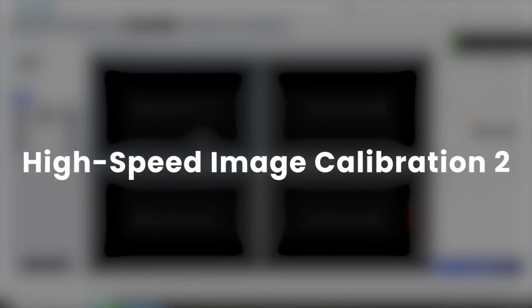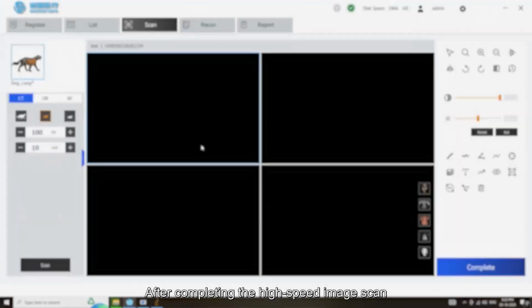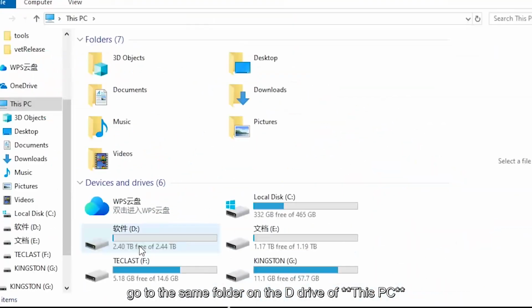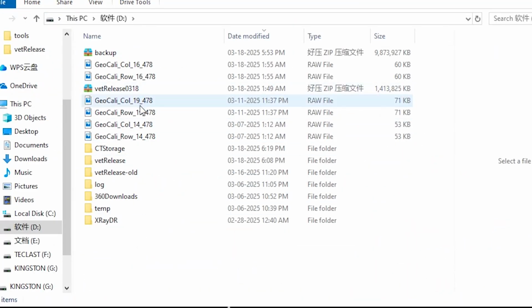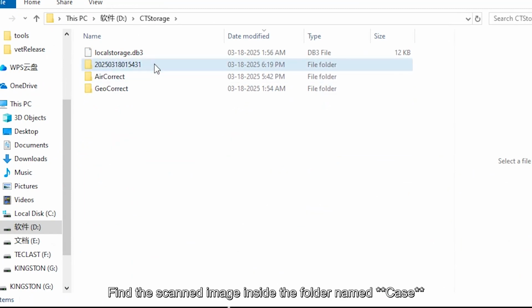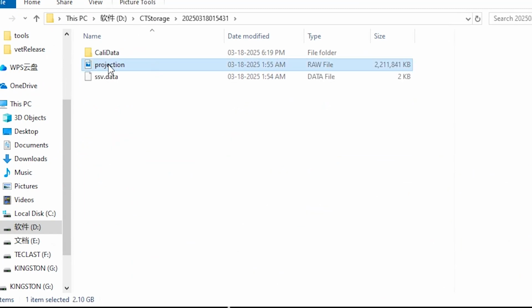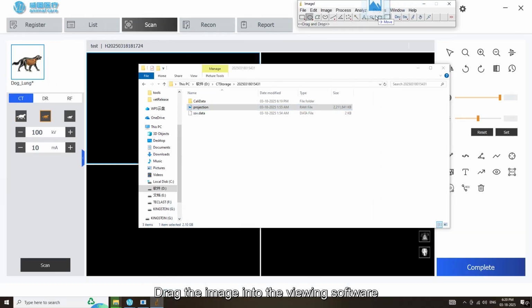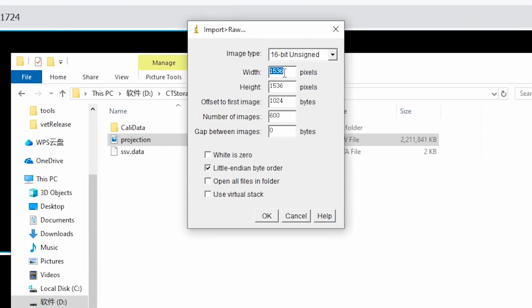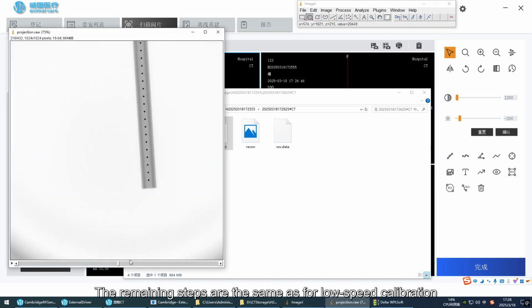14. High-speed image calibration 2. After completing the high-speed image scan, go to the same folder on the D drive of this PC. Find the scanned image inside the folder named CTStorage. Drag the image into the viewing software. Select 1024 x 1024 for viewing. The remaining steps are the same as for low-speed calibration. Repeat the process until the image aligns seamlessly from start to end.